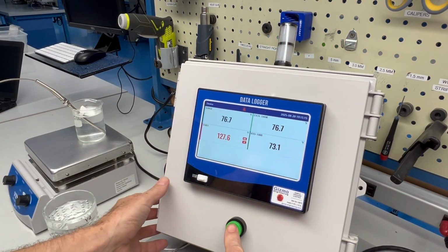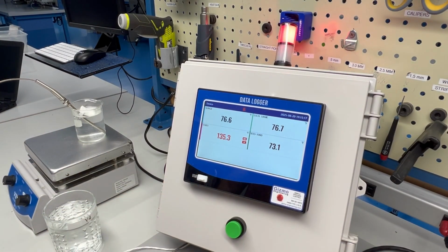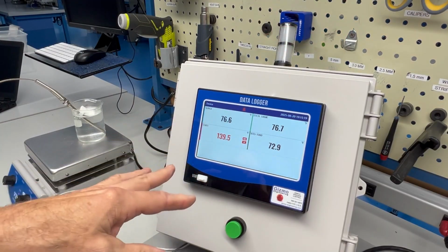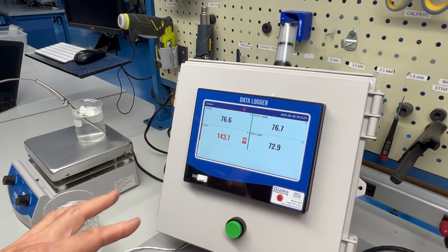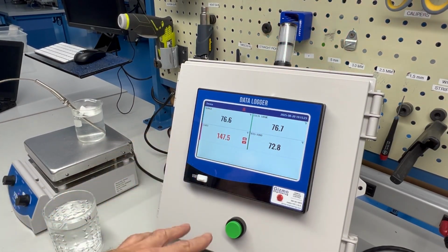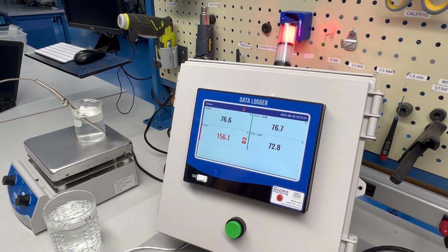We can silence that with a button here. So it's very convenient to silence. You don't need to go into sub menus and figure out how to silence it. You just push the button and it'll silence it for 30 minutes if you want. You can disable that feature, but I think it's a good feature. The snooze alarm is what we call it. And every 30 minutes, the alarm will sound again, and you have to acknowledge it again.